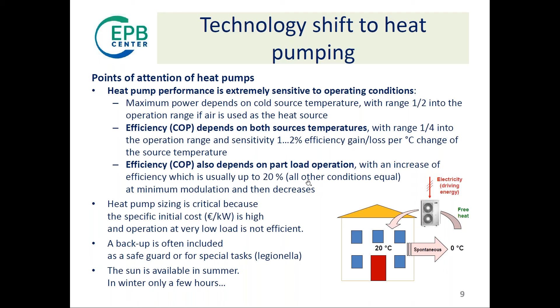So another difficulty, the heat pump sizing is critical because the specific initial cost in euro per kilowatt is much higher than for a boiler. Plus, you may want to use a backup as a safeguard or for special tasks like Legionella and so on. So this technology is nice, but you have to care about some more things.